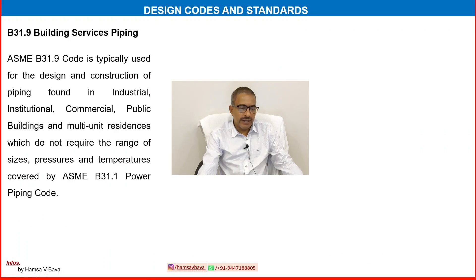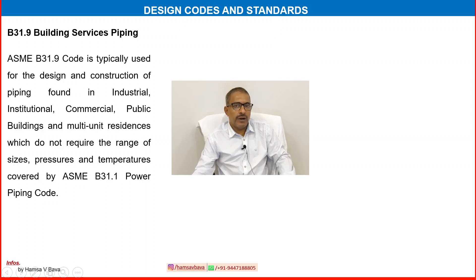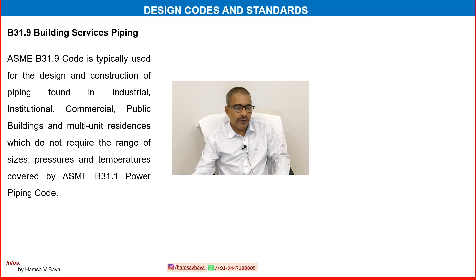It is pending on some of the ASME codes — B31.9, Building Services and Piping. The major areas we have covered include oil and gas, petrochemical, fertilizer, power plant, etc. But some other important areas also need to be covered. ASME code B31.9 is typically used for the design and construction of piping found in industrial, institutional, commercial, public buildings and multi-unit residences which do not require the range of sizes, pressure and temperature covered by ASME B31.1 power piping code.